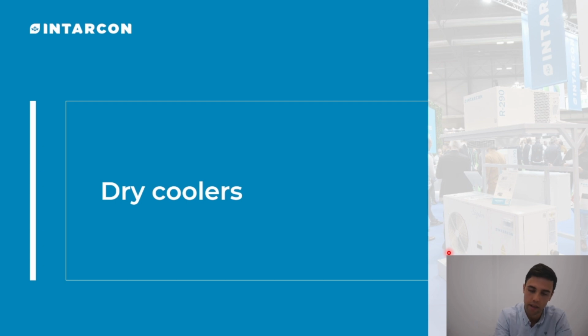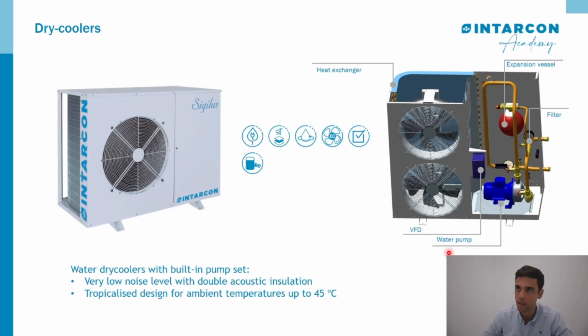Finally, let's see the last key component in the system, that is the dry cooler, that integrates the hydraulic group. The main features are a very low noise level, thanks to the double acoustic isolation, properly designed for noise-sensitive environments such as hotels. It also has a tropicalized design for an ambient temperature of up to 45 degrees, and an optimized heat exchange coil to dissipate the heat. Here we can see a render of this equipment, with the heat exchanger.